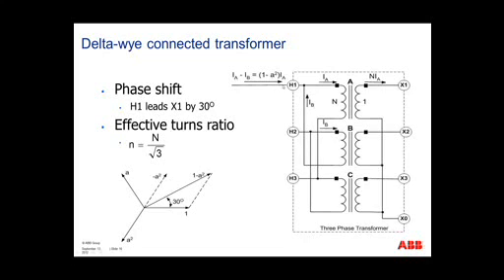We do our nodal analysis at H1. We can see A minus B. We plot that vectorially, and we can see that there is still a 30 degrees phase shift, where the high side leads the low side by 30 degrees. Keep in mind that when you do have this delta connection, you will have an effective turns ratio by a square root of 3.